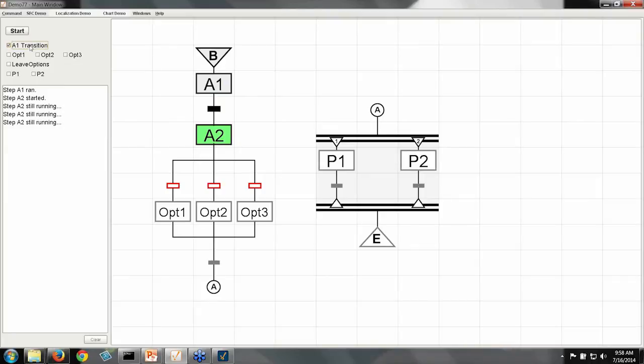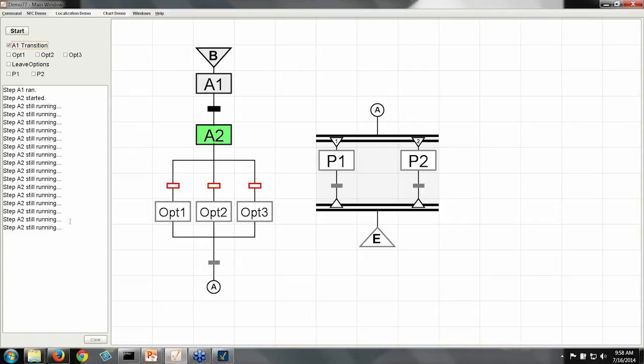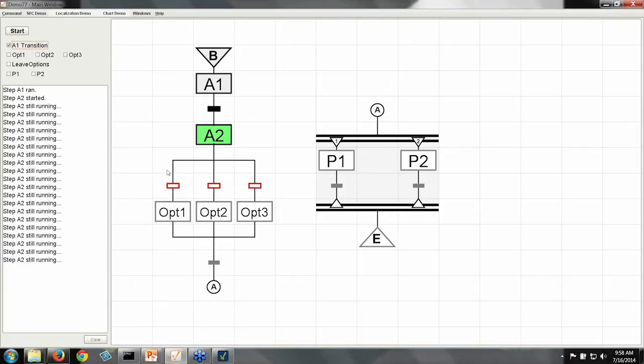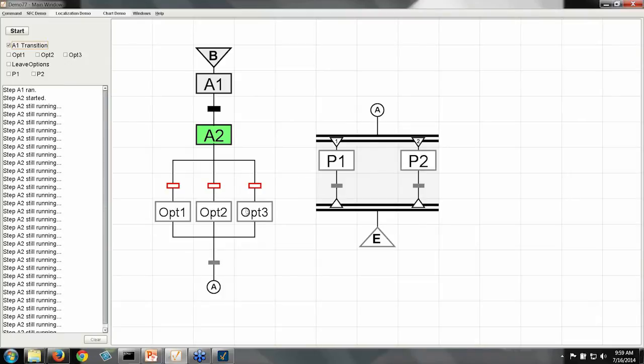And now we've got a little bit of a different configuration. So first of all, A2 is configured a little bit differently than A1 was. A2 is doing continuous work while it's running. So here it is still running, and it'll keep running until one of these three transitions becomes true. And when you have transitions set up in this branched manner, this is like an or. I'm either going to go down this branch or this branch or this branch, but I'll never do both two branches or three branches at a time.